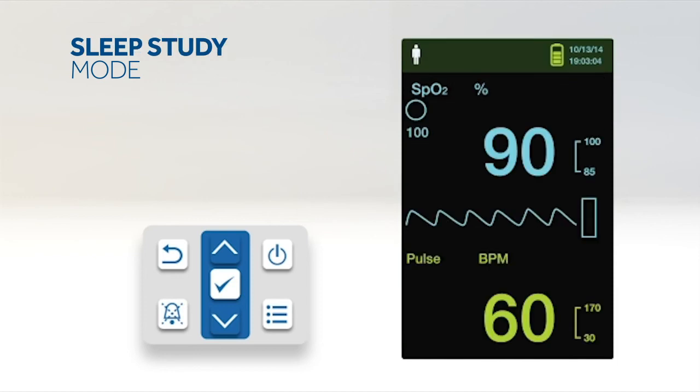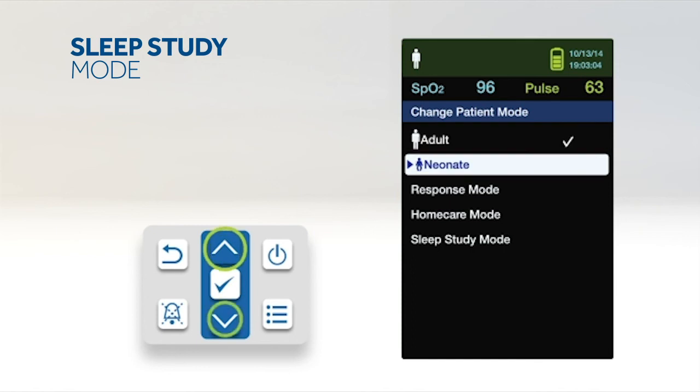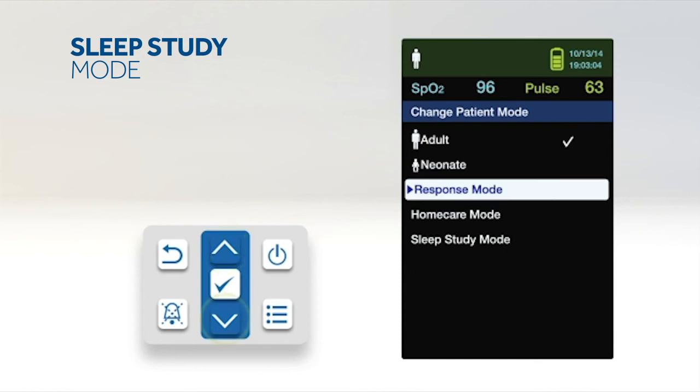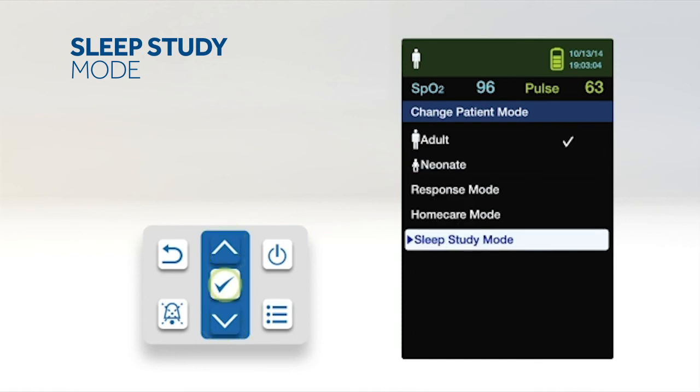When a sleep study will be performed on a patient, set the monitoring system to Sleep Study Mode. The alarms will be silenced and the screen will be dimmed. To set Sleep Study Mode, access the Change Patient Mode menu, press the up or down button to highlight the Sleep Study Mode menu, then press the OK button to select Sleep Study Mode.